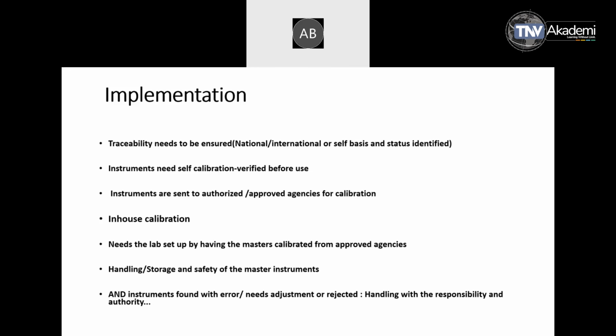Also, status identification is very important. Status identification means this item is under calibration or not, this item is for indication purpose only, this item is under the self-calibration scheme, or this item is by the external calibration team. Why? Because when we are going as a first party, second party or third party auditor, particularly in the third party auditor case, time is a very crucial element. We have very little time most of the times in an auditing situation. So if we unnecessarily waste our time by picking up an instrument wrongly and trying to find out the national traceability where it may not be required.